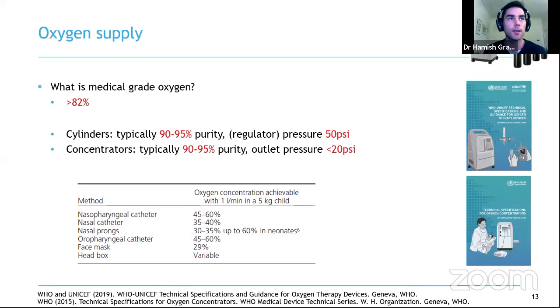The reality is that the oxygen in cylinders is derived from exactly the same process as concentrators, so pressure swing adsorption, PSA. And typically when we test the cylinders in most hospitals, it has a purity of 90 to 95%, similar to what comes out of a functioning concentrator. To increase the concentration up to 99% is very energy intensive, and at least in lower resource settings is rarely done and rarely provided. The main difference between cylinders and concentrators is the outlet pressure. And this is really relevant if you're attaching oxygen to a ventilator or to something else that needs that higher outlet pressure. And I would say there are ventilators that can run off the lower pressure from a concentrator.